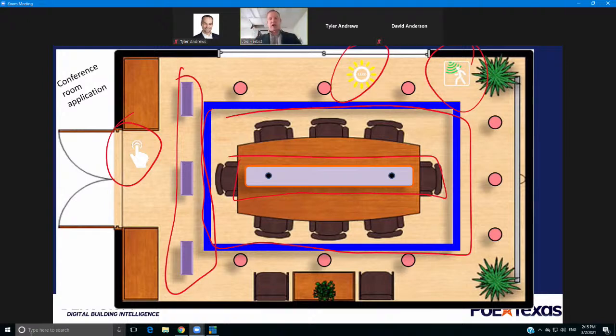So I've now got three different vantages into the exact same physical place. In this first example, I'm going to take you through four different technologies of lighting, just to be difficult: a phase dim downlight, a 0 to 10 high voltage on the front, pulse width modulated RGB cove lighting, and a constant current going to the up-down CCT fixture.